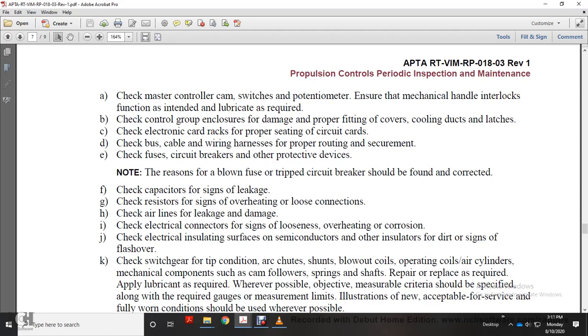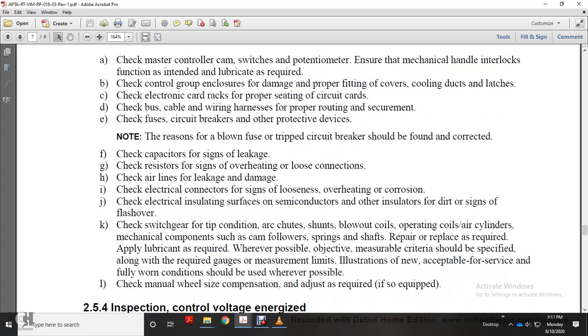F. Check capacitors for signs of leakage. G. Check resistors for signs of overheating and loose connections. H. Check air lines for leakage and damage. I. Check electrical connectors for signs of looseness, overheating, and corrosion. J. Check the electrical insulation on semiconductors and other insulators for dirt and signs of flashover. K. Check switchgear for trip condition, arc chutes, shunts, and blowout coils. Operating coils and other mechanical components such as cam followers, springs and shafts should be checked, and replaced as required.